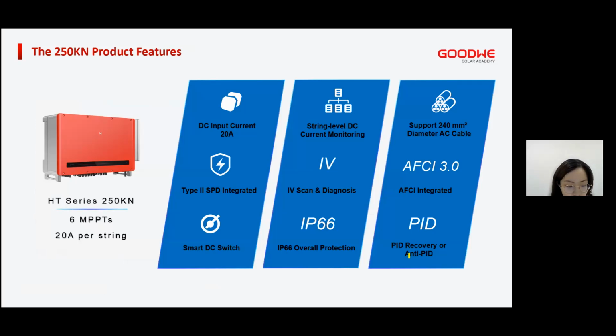Now let me introduce our latest utility products, HT250KN. This product is specially designed for large current PV modules, such as the 210 millimeter PV modules. So the maximum DC input current is 20 ampere per string. And we have also upgraded the safety functions, such as the Type 2 SPD on both DC and AC sides. And we've also upgraded the AFCI functions to prevent fire accidents.